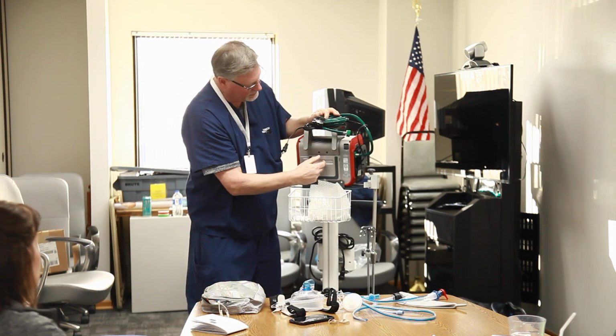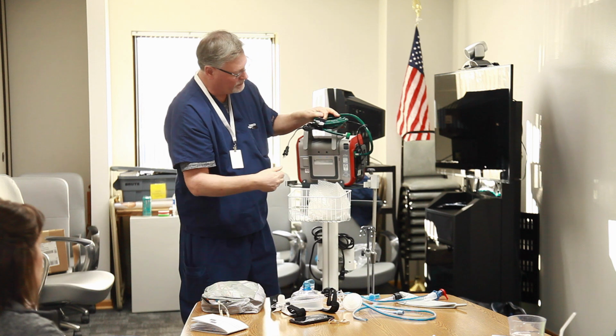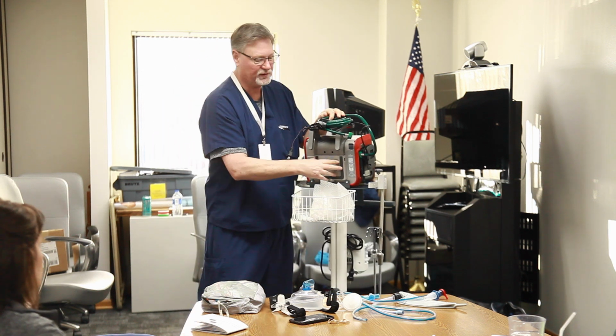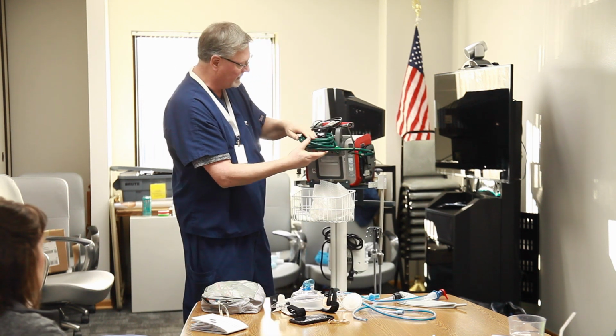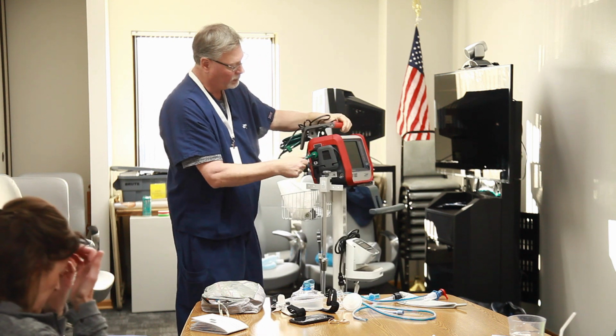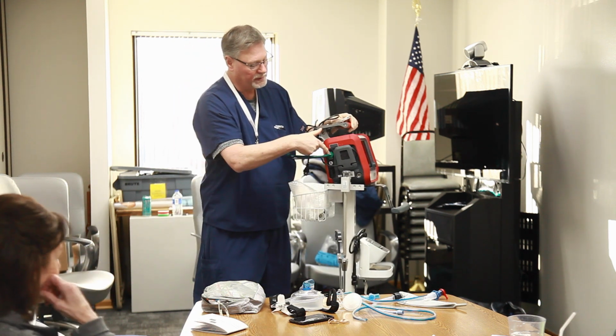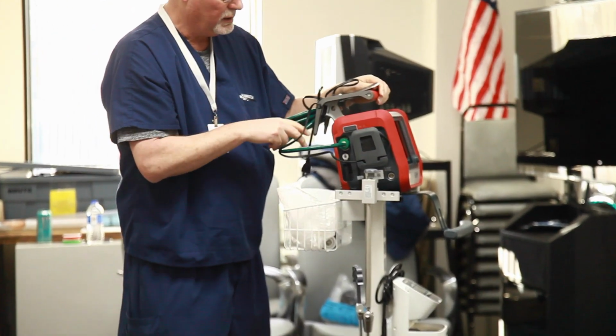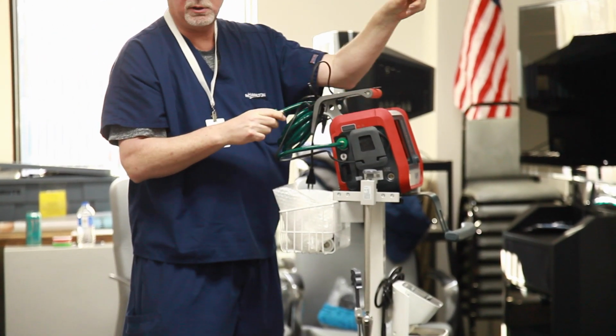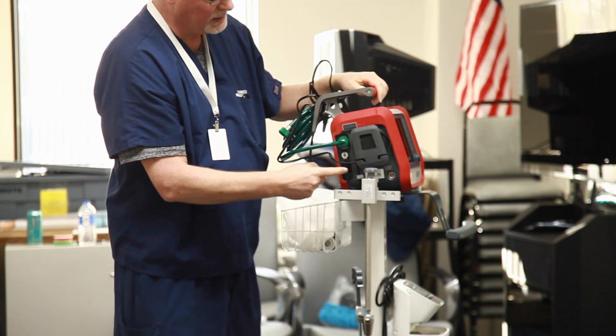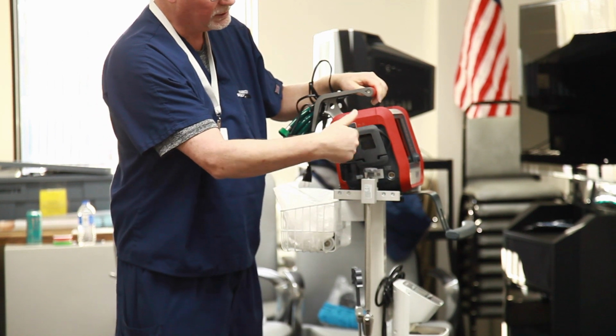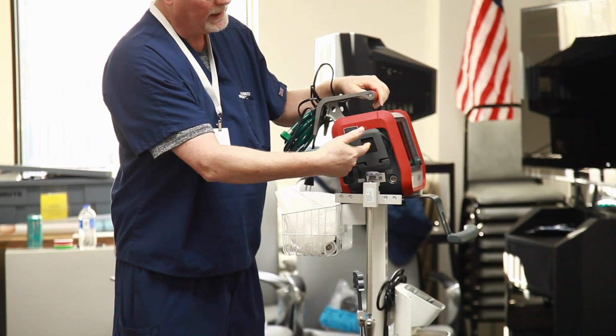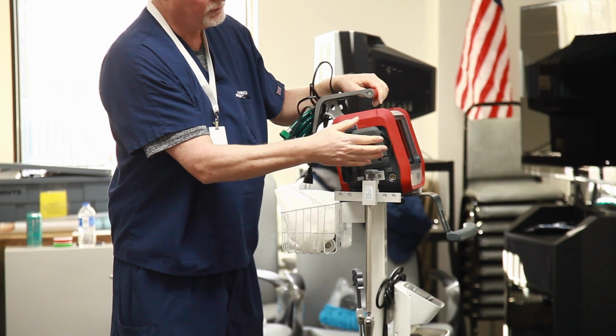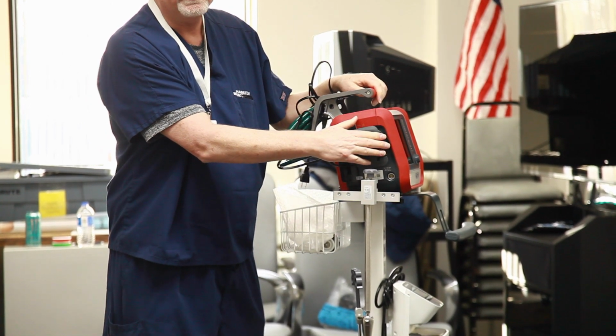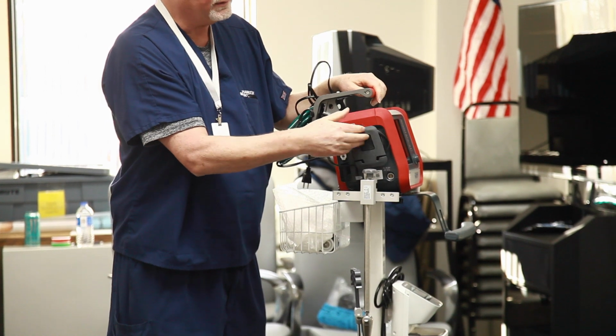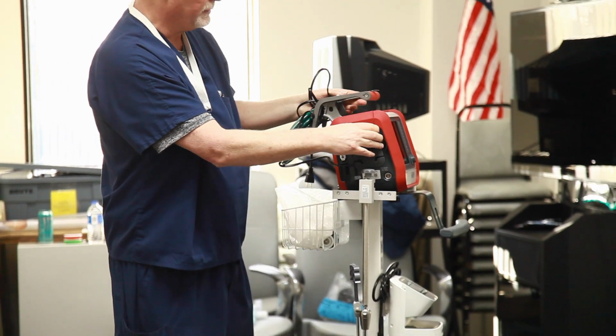Back here, we do have a little dust filter. Just take that out and wipe it off with a little damp cloth or something. Inside there is a HEPA filter before it gets to the patient. This side is where your main stuff gets hooked up. You got your O2 tubing from the wall. You will have a quick connect or something like that to plug into the wall. So that's just a little easy plug-in, 110 power. The extra cord can wrap around here. And just a little filter here for the fan and stuff inside there. Again, dust that off with a damp cloth or something when it gets dirty.